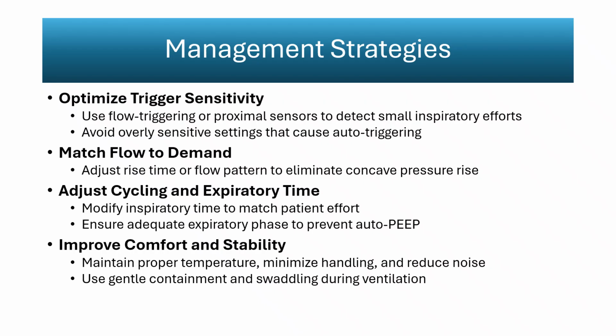Cycling and expiratory timing also play a central role. Inspiratory time should align with the infant's neural inspiratory duration so that the ventilator ends the breath when the infant intends to exhale. If inspiration ends too early, the infant receives an incomplete tidal volume. If it ends too late, the infant is forced to exhale against ongoing flow. Adjusting the inspiratory time restores this alignment. Adequate expiratory time is equally important. If expiration is too short, air trapping and intrinsic positive end expiratory pressure develop, making it harder for the ventilator to detect triggers and increasing work of breathing.